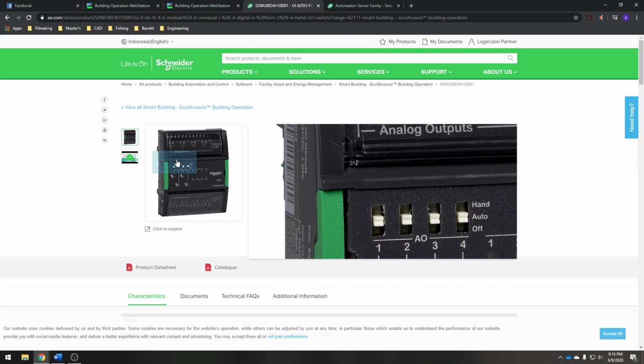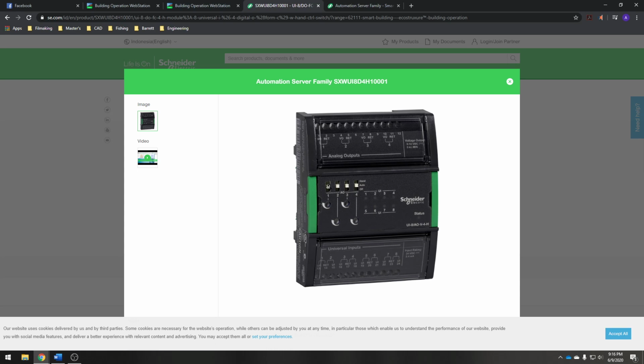So you'll come in here, you'll see this, just flip the switch on and verify, just double check visually that this is spun all the way up, because there are cases where we may want to spin it down in hand, and someone may forget to put it to 100. So prudence would tell you, the operator, make sure this potentiometer is at 100, click it in hand, and either that valve will open, the chiller will start, or that pump will run at 100%.